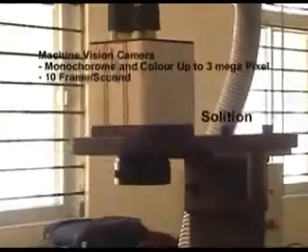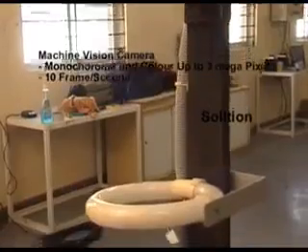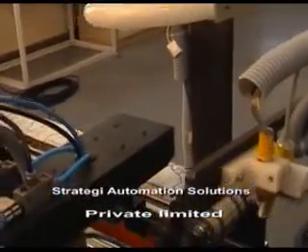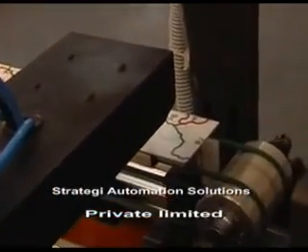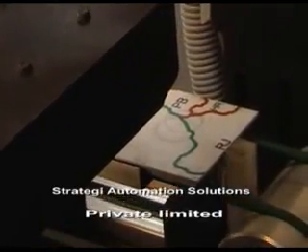The 3 megapixel camera is used to detect the part that has come in on the infeed conveyor and its orientation. This information is transmitted on the serial port to the PLC. Each part can have four orientations: 0, 90, 180 and 270 degrees.